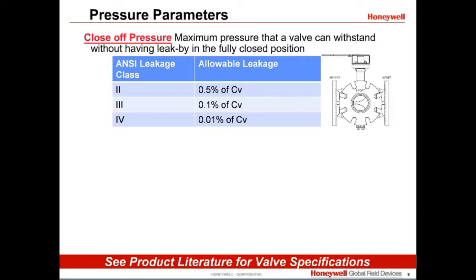Almost all Honeywell control ball valves have an ANSI Class 4 leakage rating. This means that in the fully closed position, the maximum leakage between the valve ports is 0.01% of the rated CV. Close-off pressure is also important because the valve must be able to close against the system pressure.